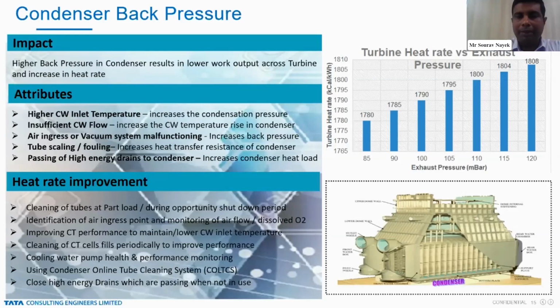The CT performance is another very important aspect, and we should regularly clean the CT fills to improve the performance of the cooling tower, and this will give the CW cooling water inlet temperature as a design value. Second, CW pump health monitoring is also very important and we should periodically check the performance of the CW pump so that we get the sufficient CW flow which is required for the condenser performance.